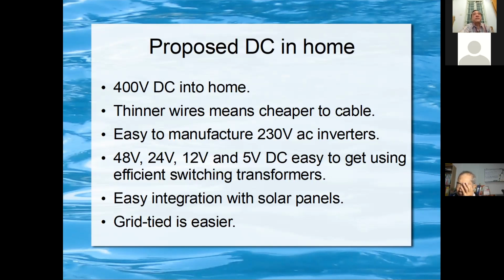The wire doesn't need to be much thicker. If you want to use the same size wire, then instead of 400 volt, you run at 320 volt, which is the peak voltage of 230 volt AC. So if you run 320 volt DC, you don't need to change any wiring. 400 is just a nice round number.